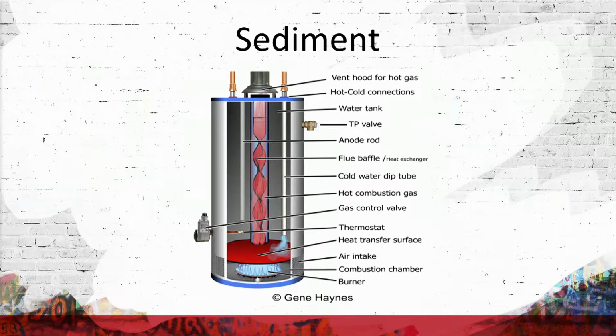In a piece of equipment like this, the sediment acts as an insulator. What does insulation do? It keeps heat in and prevents heat from getting out. So the sediment on the bottom is the insulator, and the flame underneath it is trying to get through. You're running that equipment harder than needed, correct?